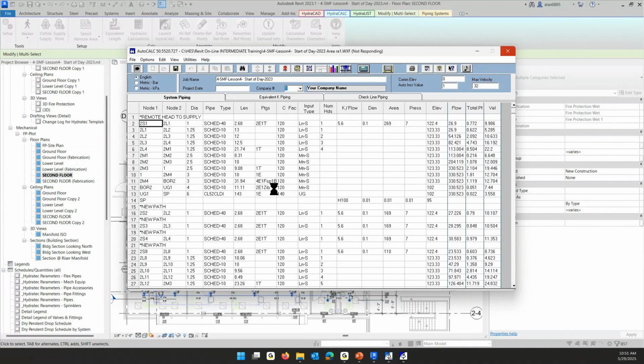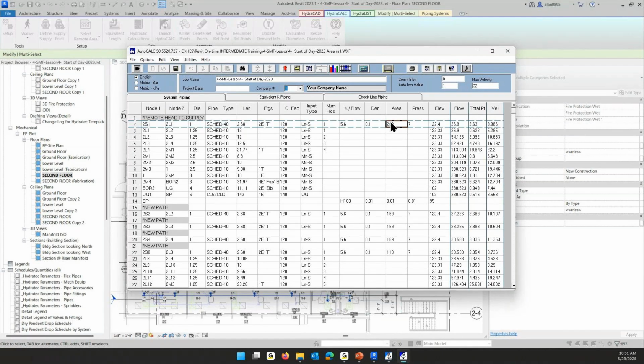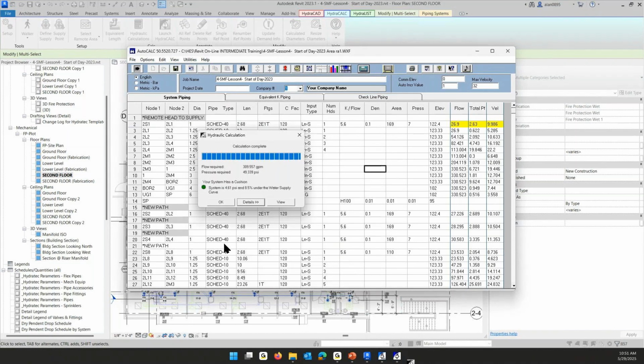That crazy change you made. Right, I shot myself in the foot on purpose. I'm going to change that back to 169 and then run the calc again. And look at that. Even with 1.25 inches and 2.5 and everything else the same, we're under the curve by 4 pounds instead of being over the curve by 20 pounds or 18 pounds or something.